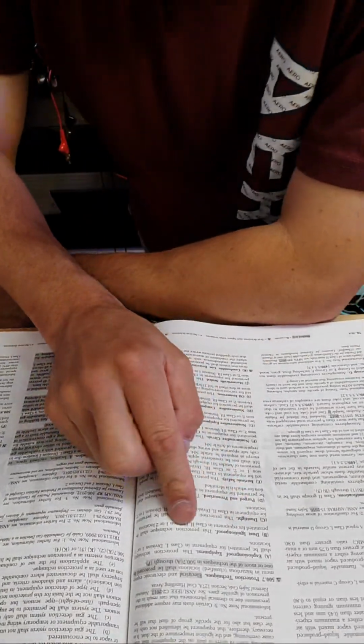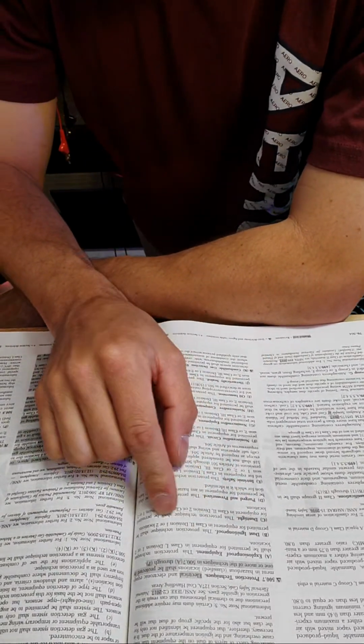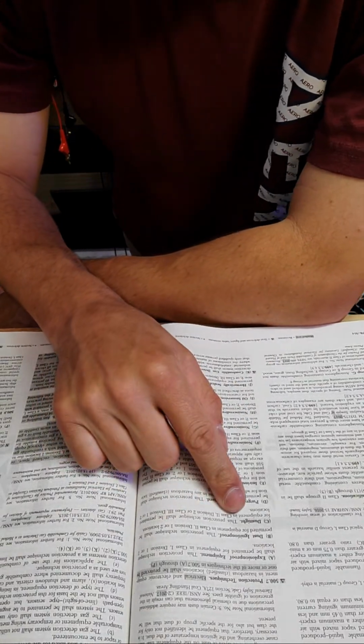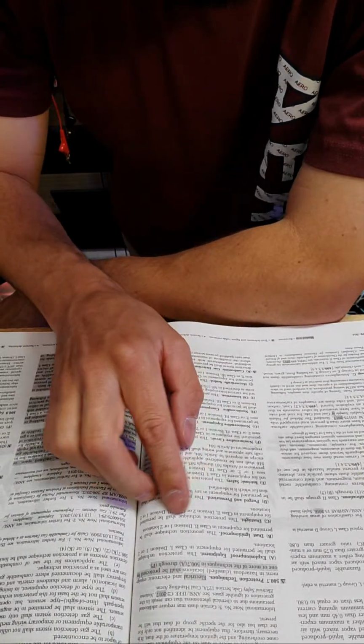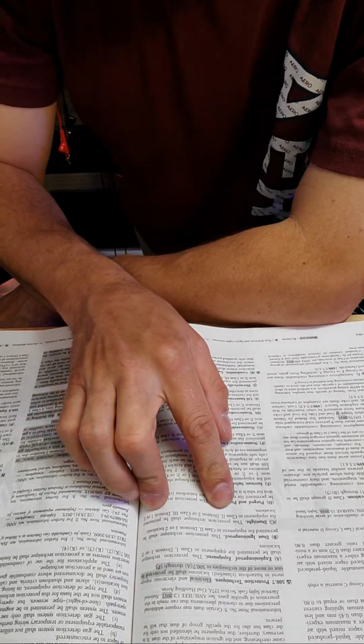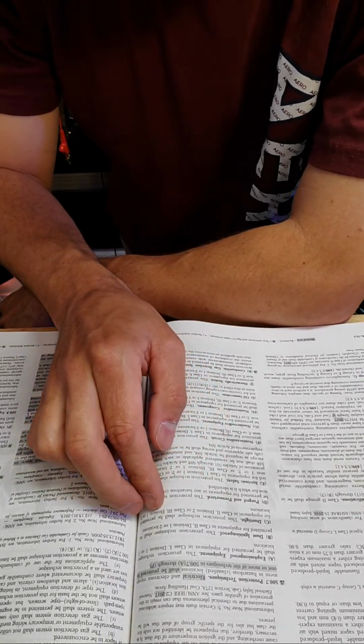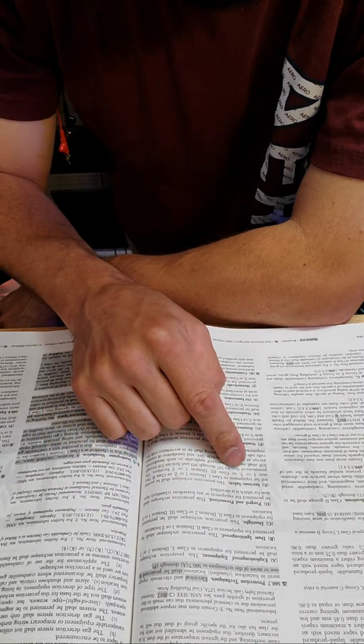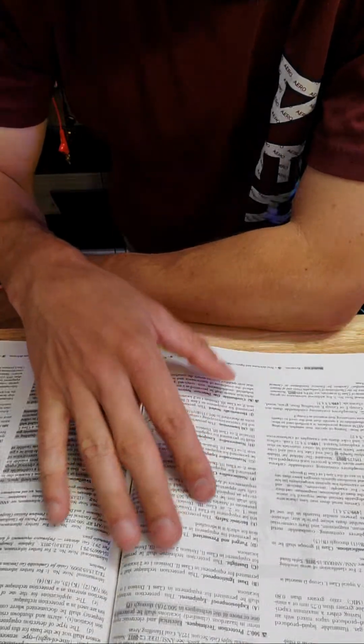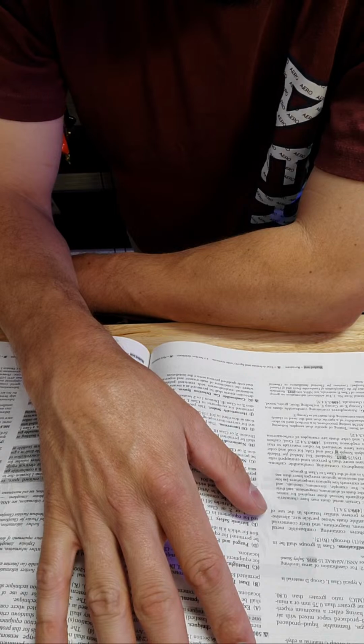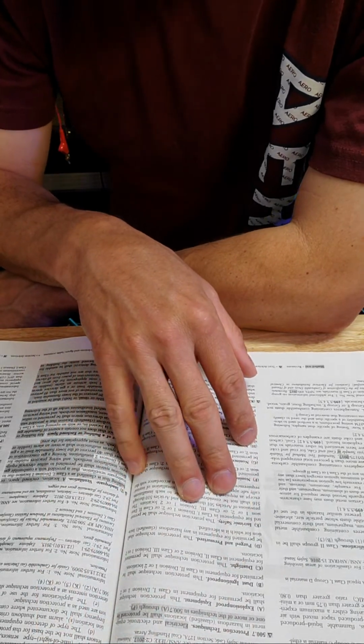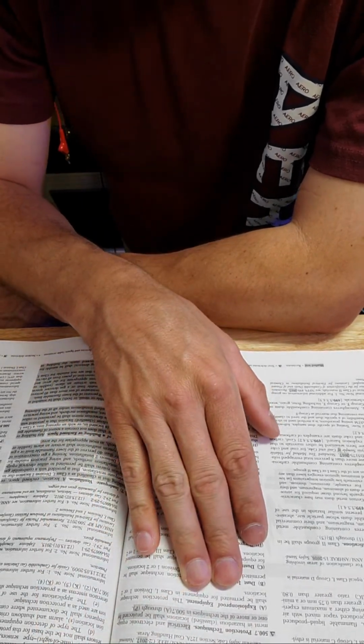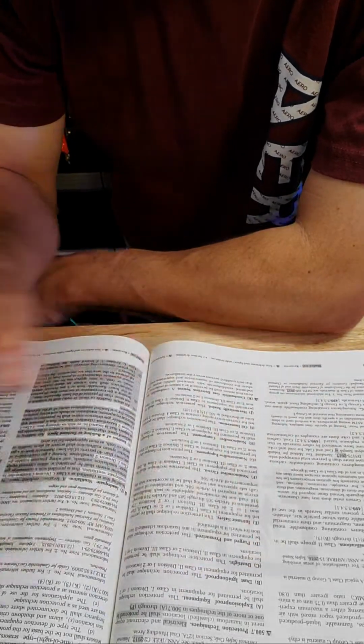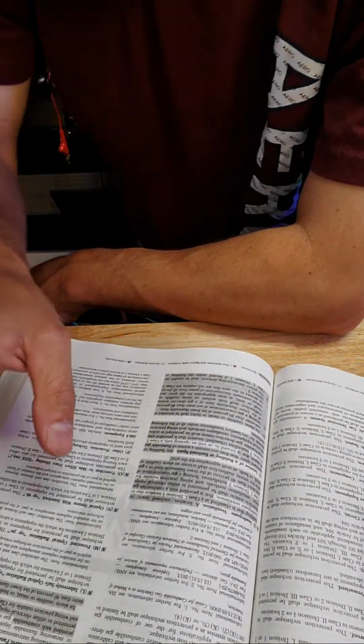Dust ignition proof would be Class 2, Division 1 or 2. Dust tight is a protection technique permitted for equipment in Class 2, Division 2, or Class 3. Then you've got all the requirements for the installation of a Class 2 area, which is what the dust is, and it goes on to tell you everything about how to install it.